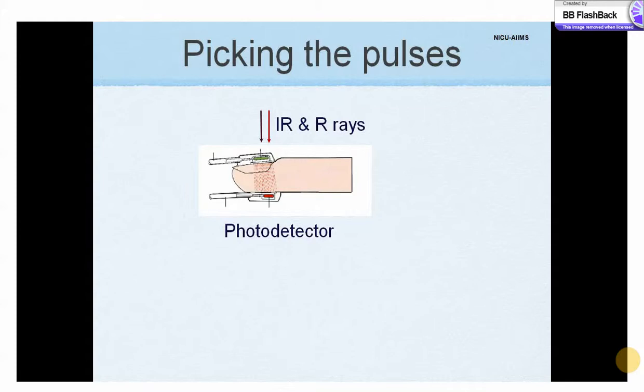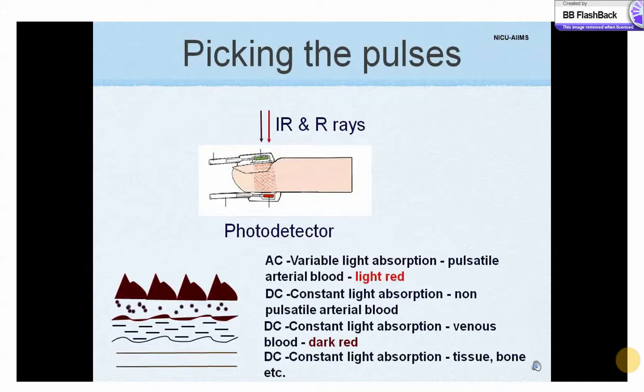Each pulse oximeter probe contains two light emitting diodes which emit red and near infrared wavelengths through a cutaneous vascular bed. A photodetector on the other side measures the intensity of transmitted light at each wavelength, from which the oxygen saturation is derived. This is based on data stored in the memory of the oximeter.